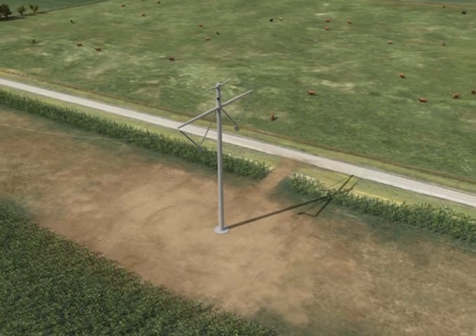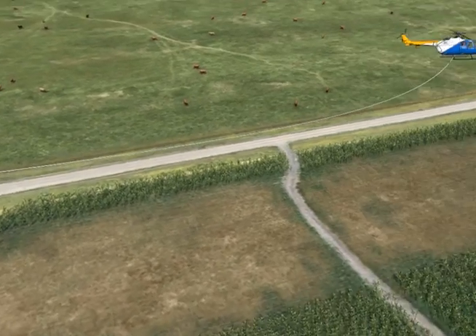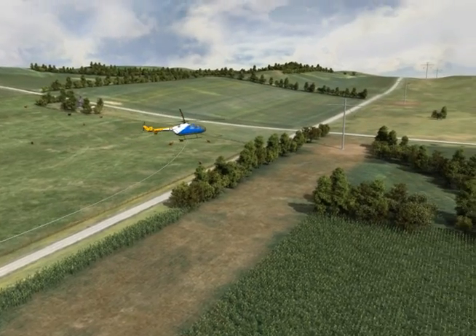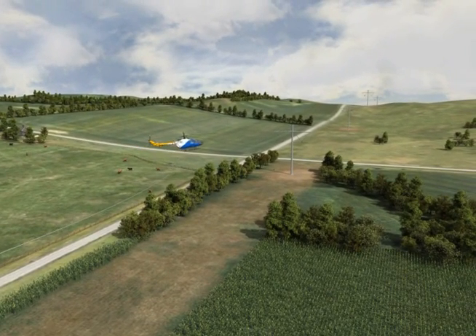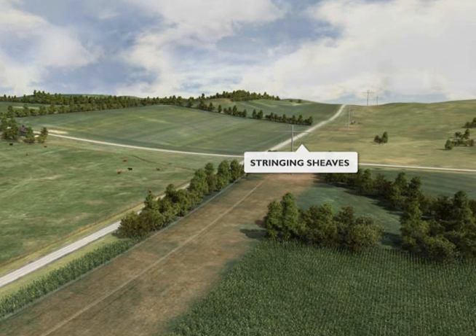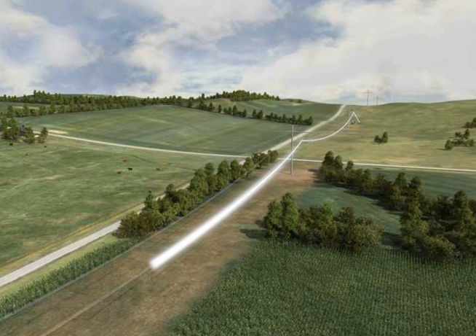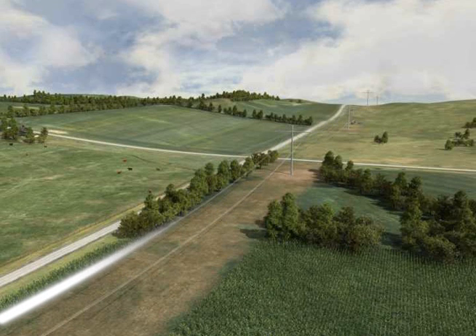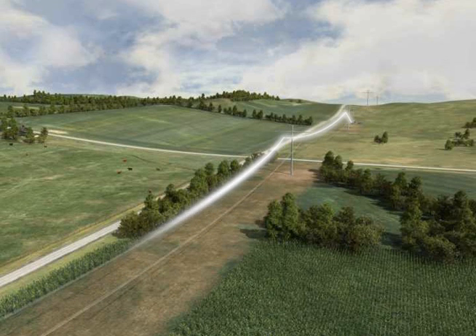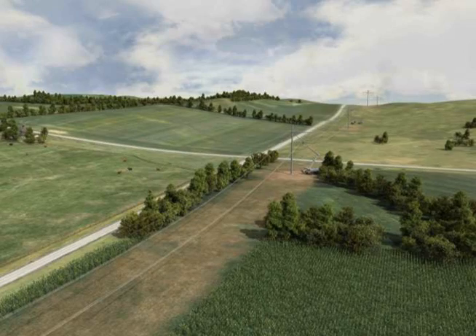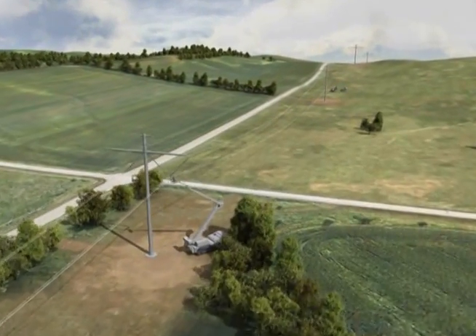After the towers are in place, crews will use specialized pulling equipment to install the conductors, ground wires, and any fiber optic cable. This process begins by first stringing pilot lines through the stringing sheaves on the structures. The pilot lines will be used to pull a stronger, larger diameter line attached to conductors and ground wires. This process is repeated until the ground wires and conductors are pulled through all of the sheaves.